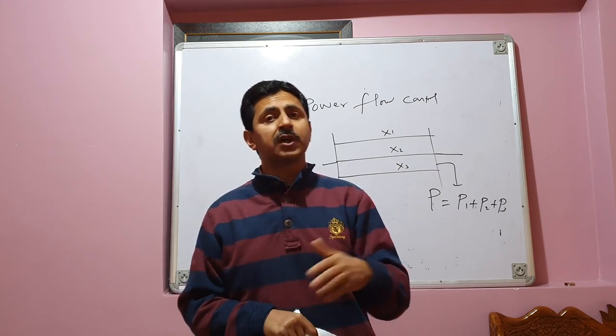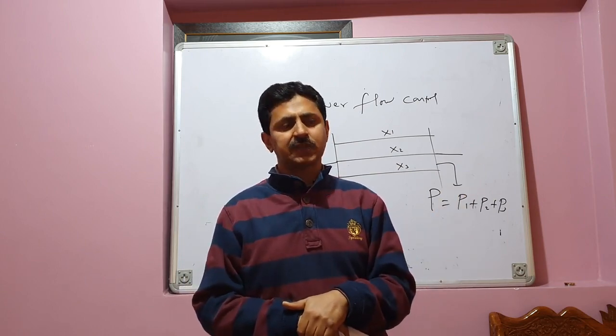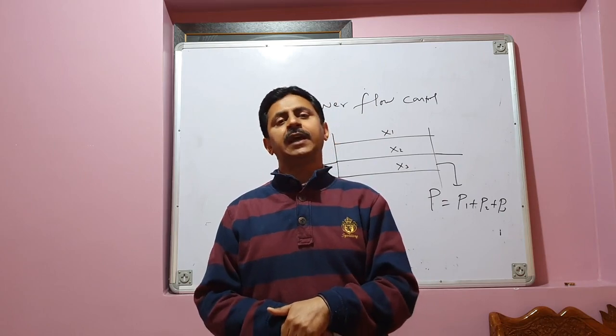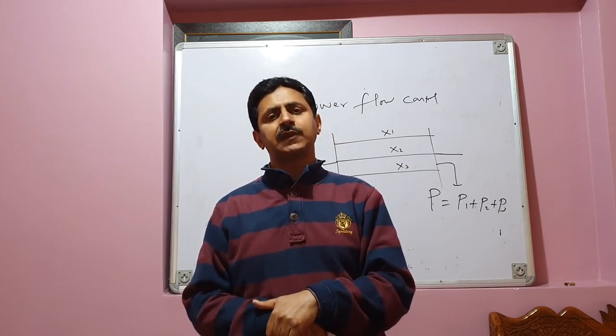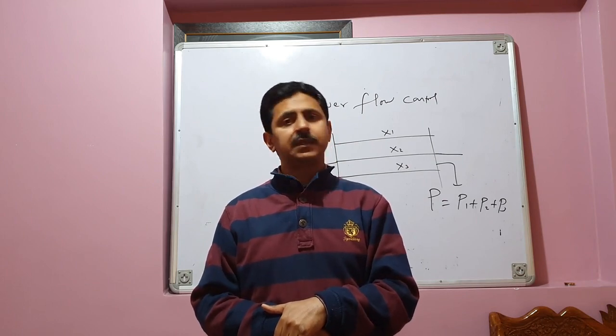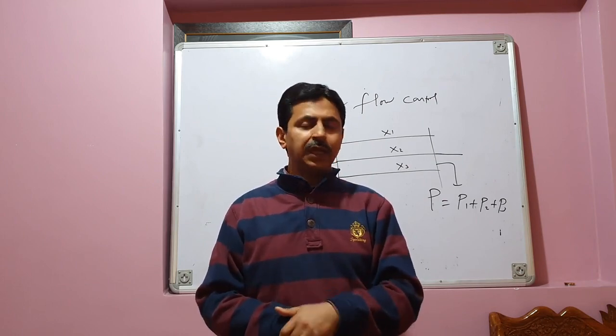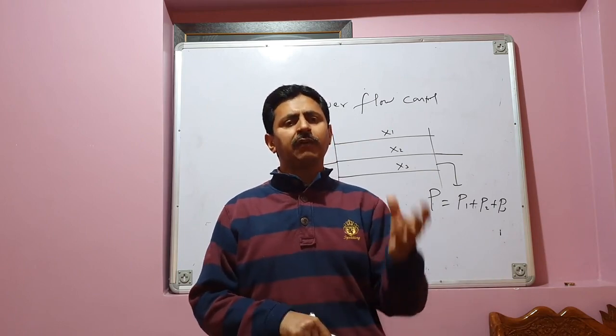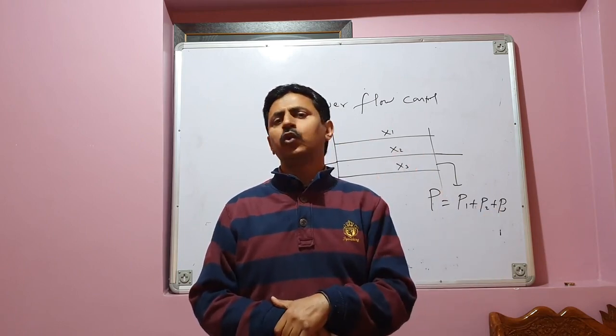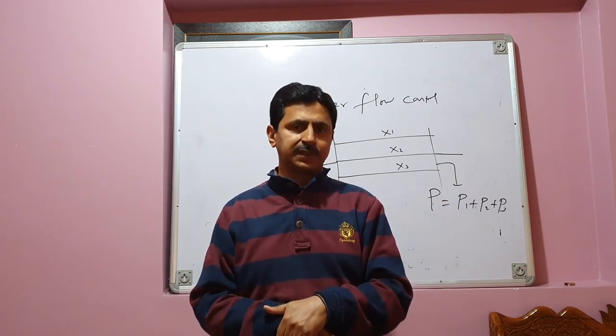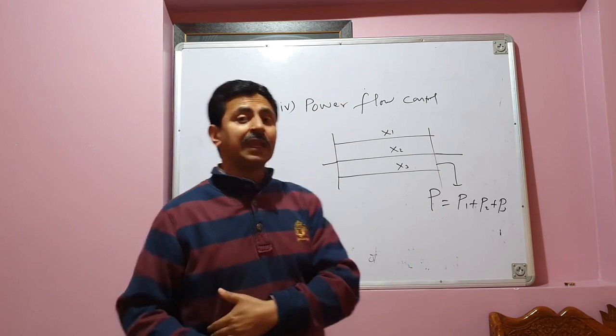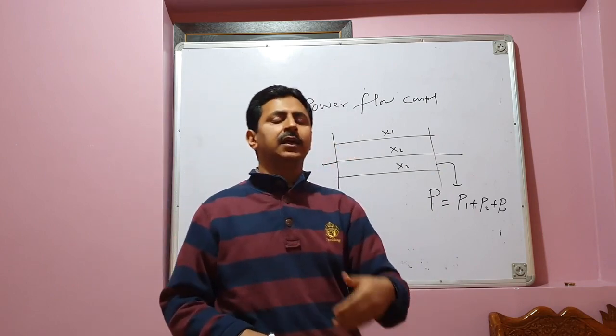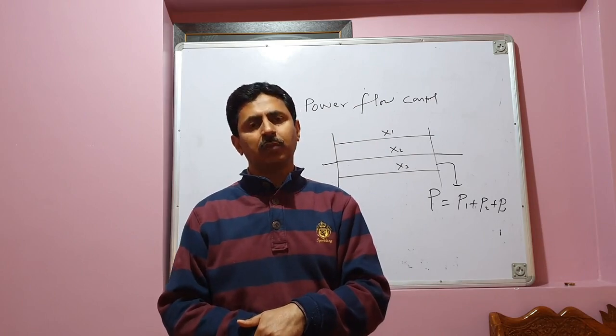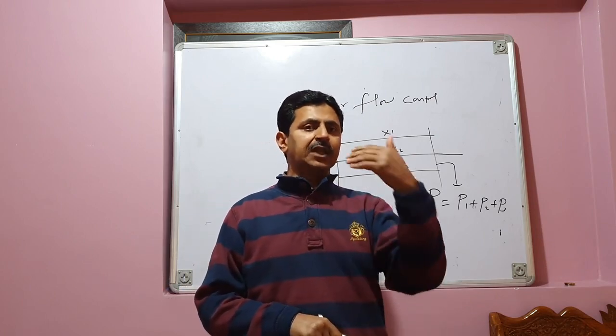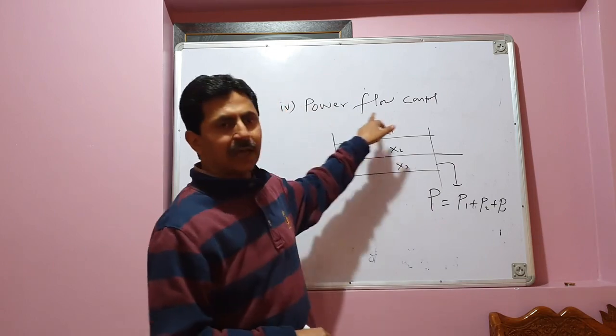So it is possible in case of HVDC power transmission system. It is an inherent advantage with HVDC power transmission. This is not possible with AC power transmission system without FACTS controllers. Here in HVDC, you can have perfect control over the flow of power, and you don't need any extra components, like FACTS controllers. So one of the main advantages of HVDC power transmission is that it is possible to have complete control over the flow of power over various HVDC transmission lines. So that's what I have written here. Power flow control is possible, which is not possible with AC transmission.